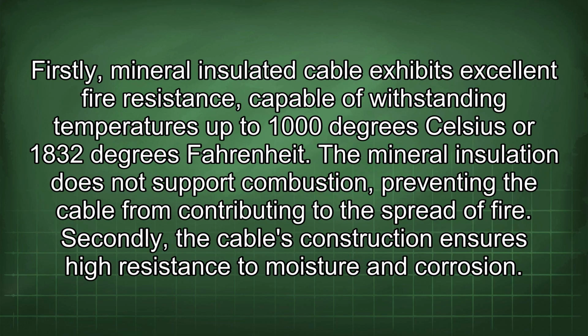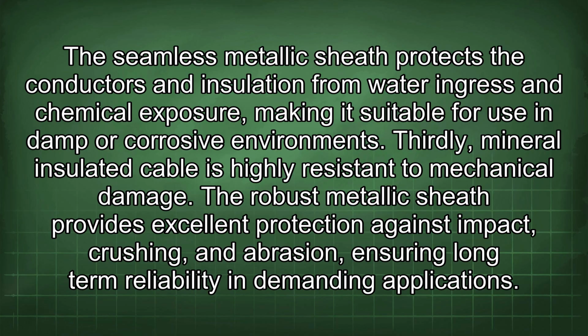Firstly, mineral-insulated cable exhibits excellent fire resistance, capable of withstanding temperatures up to 1000 degrees Celsius or 1832 degrees Fahrenheit. The mineral insulation does not support combustion, preventing the cable from contributing to the spread of fire. Secondly, the cable's construction ensures high resistance to moisture and corrosion. The seamless metallic sheath protects the conductors and insulation from water ingress and chemical exposure, making it suitable for use in damp or corrosive environments.